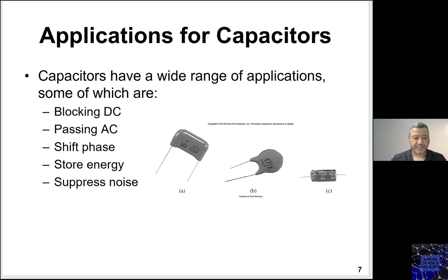So you maintain the DC inside. And very expensive instrumentation that we use, that's called the VNA, Vector Network Analyzer, we make sure that we have this DC blocking at the input of this instrumentation to protect the very sensitive RF circuitry inside. So no DC signal is allowed to enter into this instrumentation, and that's why we use some DC blocking equipment right at the input. So we block the DC from the AC.